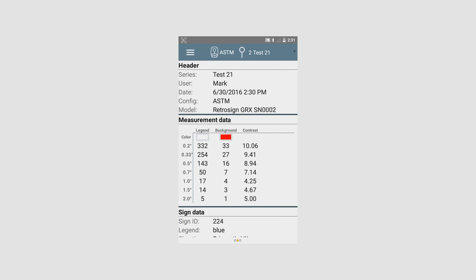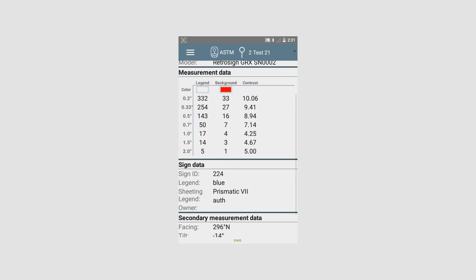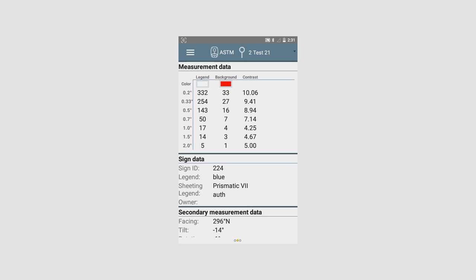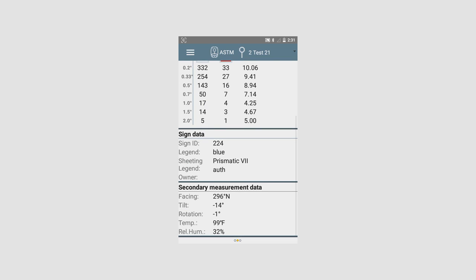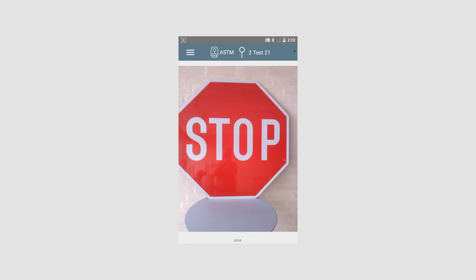On page 2, under the header, we have the basic information about this measurement. Under measurement data, we have the 7 observation angles, the legend and the background color, and the individual measurements. And the instrument has automatically calculated the contrast for each angle. Further down, we have the sign data, which we have entered before we started measurements. And at the bottom, we have what we call secondary measurement data. That's the facing of the sign, the tilt of the instrument, the rotation of the instrument, the temperature, and the relative humidity. And on the third page, we have the full-size picture of the sign measured.